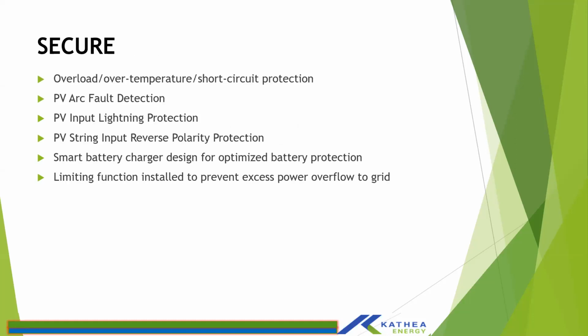And the inverter comes with built-in features for protection from overload, over temperature, short circuit, all those features are built in. So if an overload happens in your wiring, the system will quickly detect that. It has a built-in earth leakage of 100 milliamps. It also comes with built-in PV arc protection, so it can detect any arcs on your PV array, whether it's positive to negative, positive to ground, or negative to ground. It can quickly detect that and give an alarm.